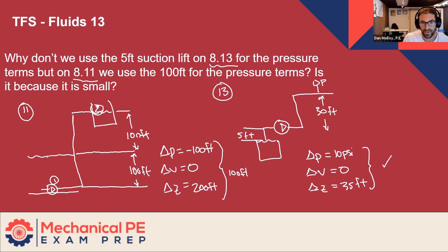It could be higher, it could be near the top. That sort of has a canceling effect. And if I were to take that all the way to extreme, I could bring this pump all the way up to the top of the water level. And it really wouldn't change what the pump is up against. It would lose all of that height on the suction side, but it would gain it all back because it has to do way less on the discharge side because it's so much closer to its target.